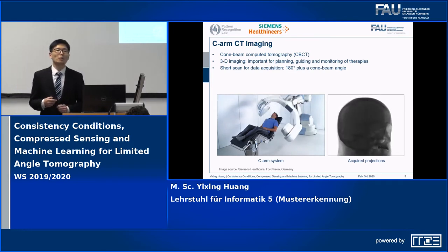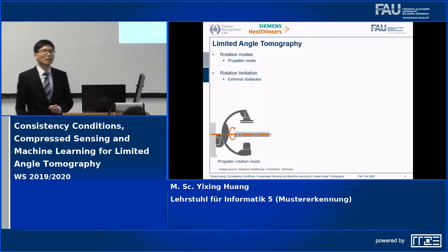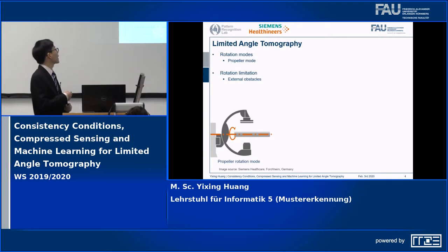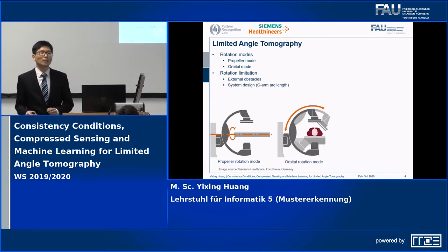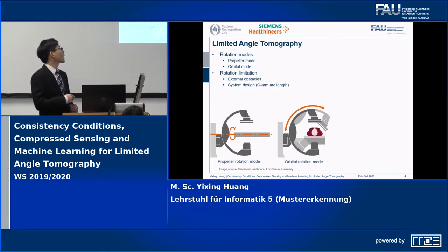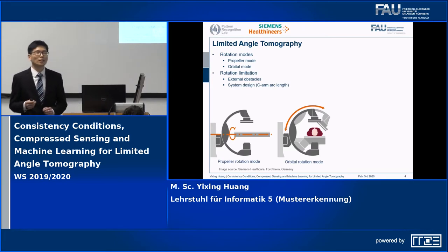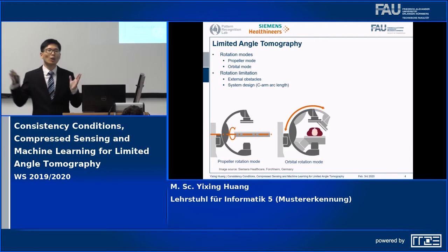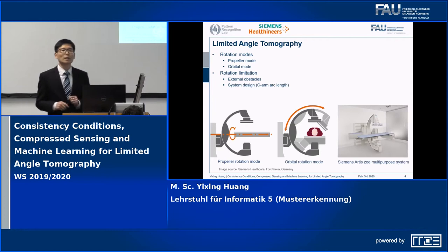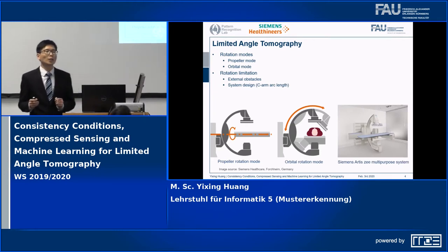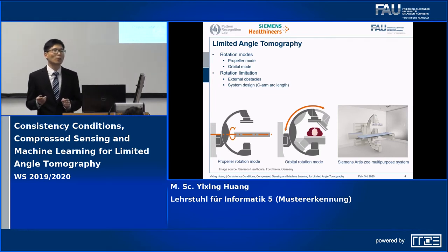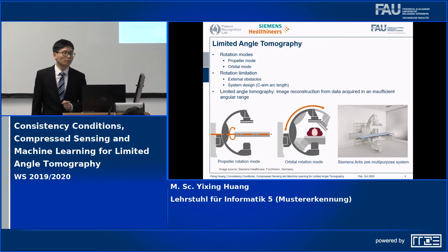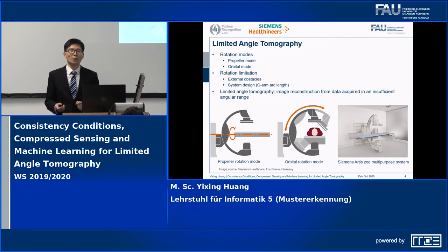Note that there is no limited angle problem in this video. However, in practice, the rotation might be restricted by some external obstacles — for example, an extra surgical device near the patient bed. Then the problem of limited angle tomography arises. There are two rotation modes in C-arm devices. The other one is called the orbital mode, where the source and the detector rotate along the arc of the C-arm. For some systems, the arc length is decided to be small so that there is more opening space for surgical operations. For example, this Siemens multipurpose system can rotate 150 degrees only. If we want to use such a system for 3D image reconstruction, then the problem of limited angle tomography also arises. So, image reconstruction from data acquired in an insufficient angular range is called limited angle tomography.